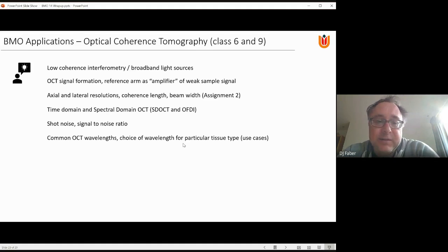One is of course the concept of low coherence and of interferometry. So it is usually a Michelson interferometer that uses a broadband light source, and the consequence of using a broadband light source is that an interference pattern will appear only at a very small position in space. So if you would elongate one arm of this interferometer, then you will only see an interference pattern at a very small specific set of path length differences or mirror positions of that interferometer.